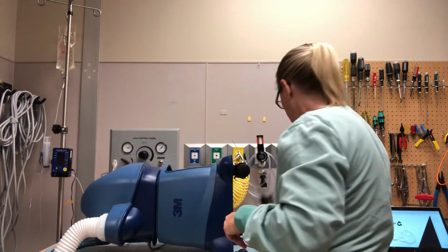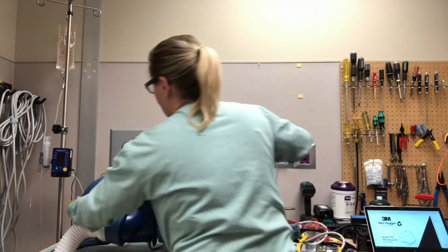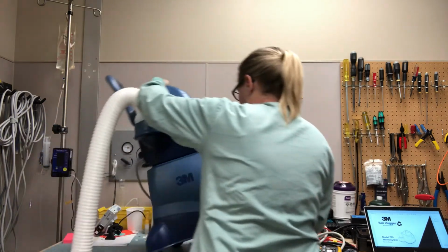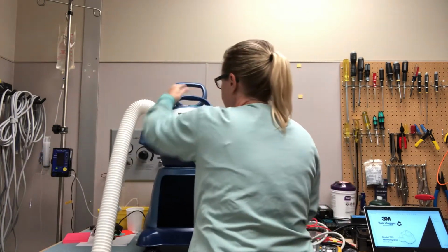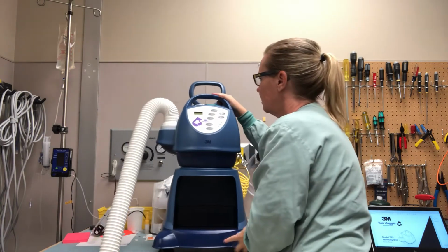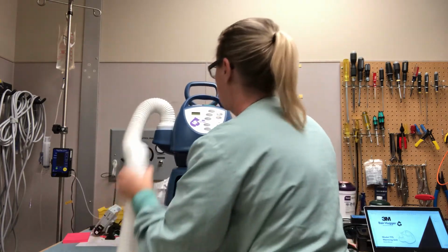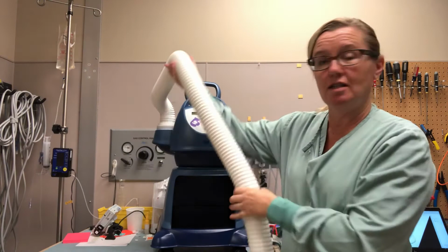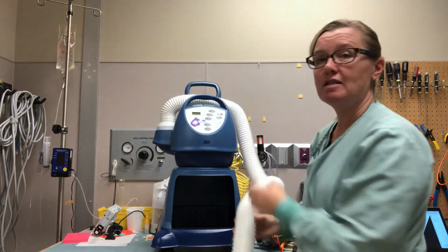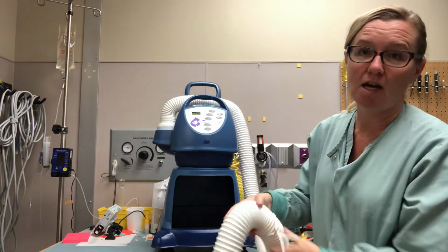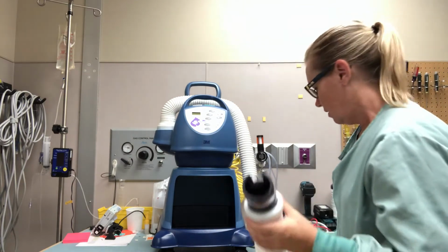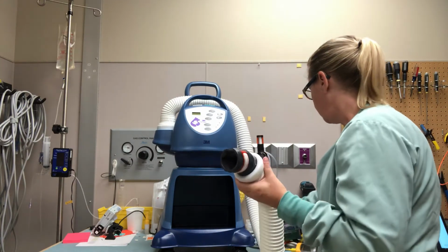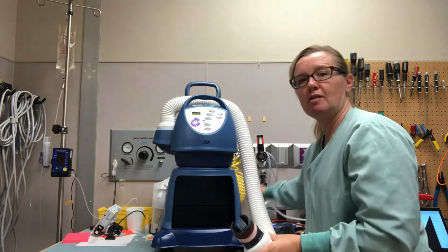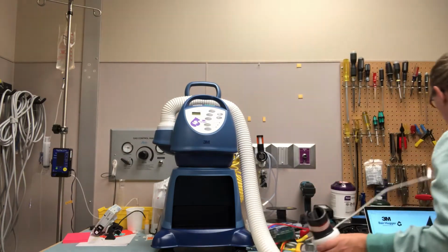Okay, now that our filter is back in, I'm going to position this back upright here. And I'm going to prep it for the first preventive maintenance test. The first test is calibrating the operating temperature. So for this test, I'm going to plug in the Bair Hugger to just a regular outlet.